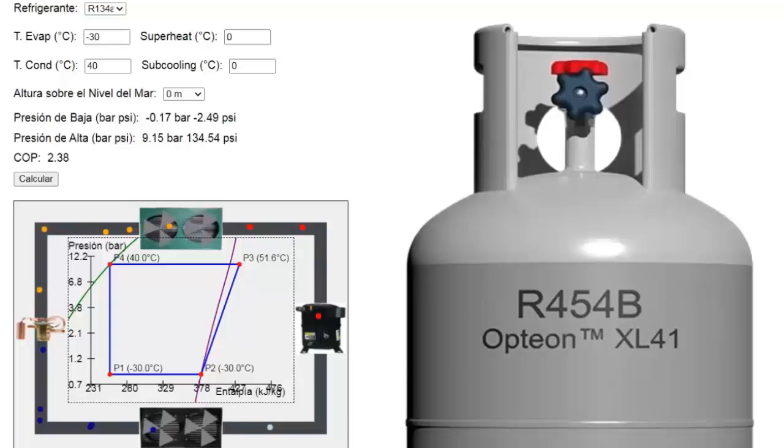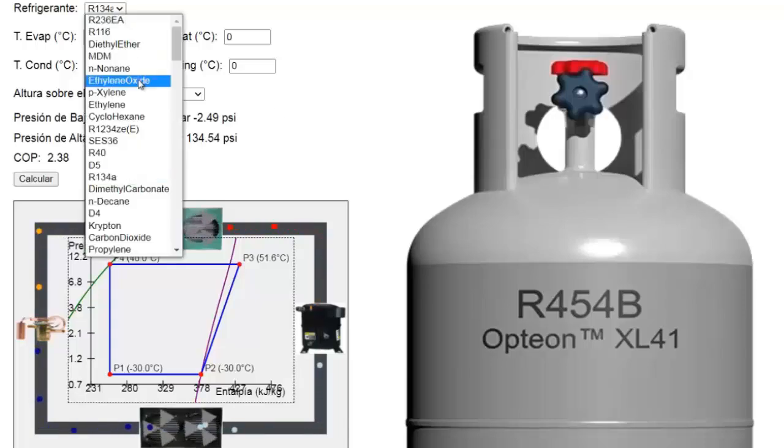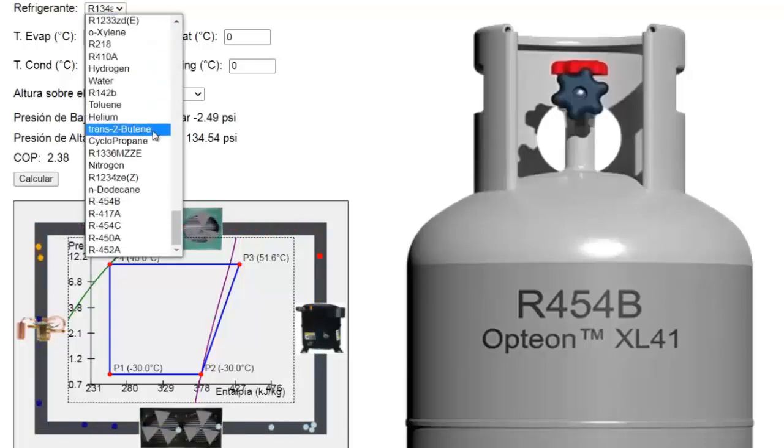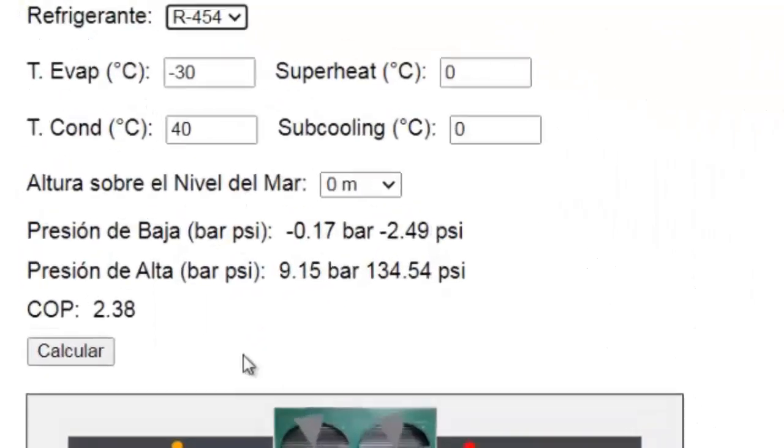Let's begin by selecting R454B in the simulator and setting an evaporation or cooling temperature of 4 degrees Celsius, which is typical for air conditioning systems.